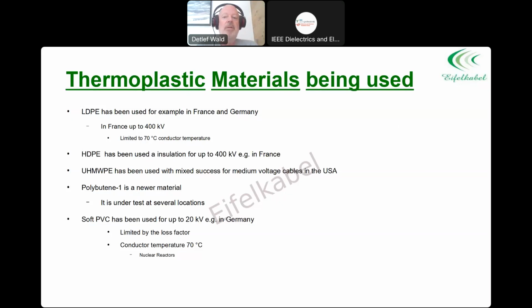Looking at thermoplastic materials, they are not that new. LDPE has been used, for example, in France and Germany, in France even up to 400 kV. Their limitation was a 70 degree conductor temperature and 150 to 160 degree short circuit temperature.